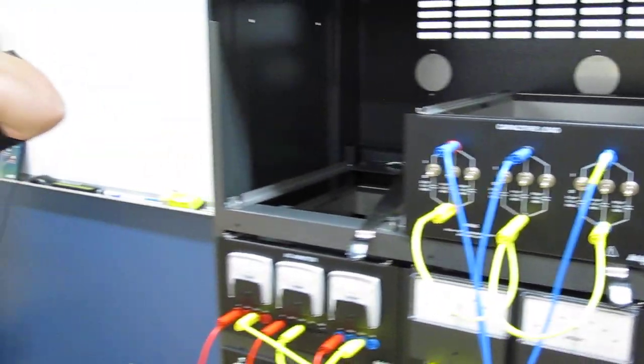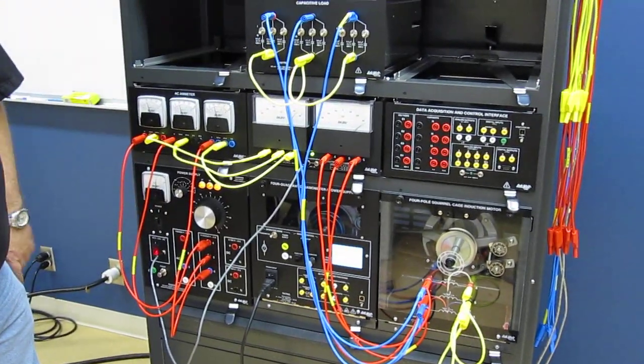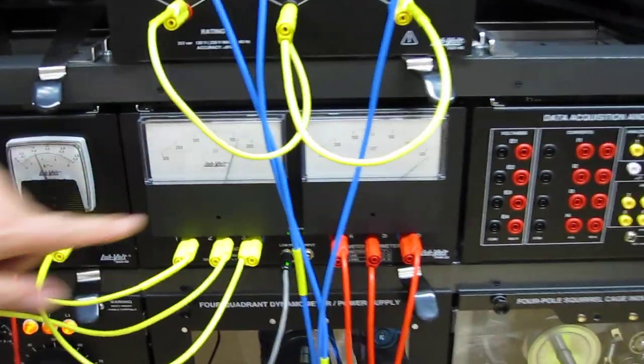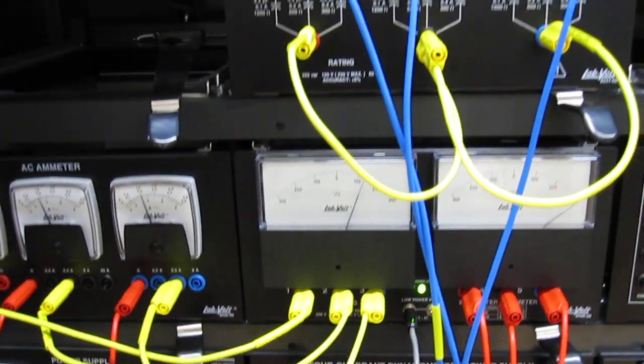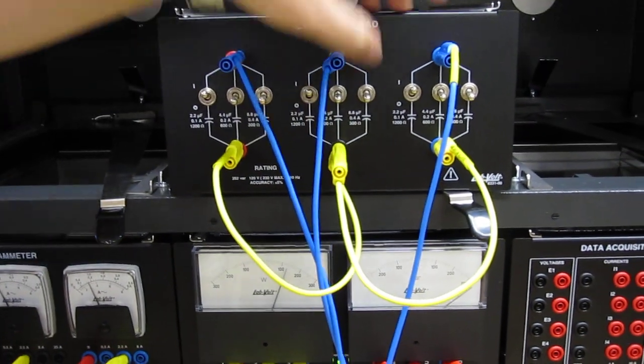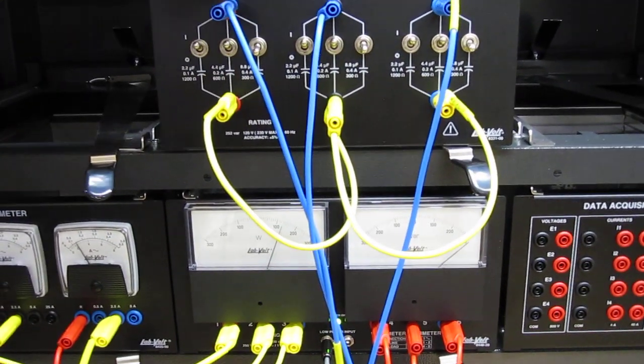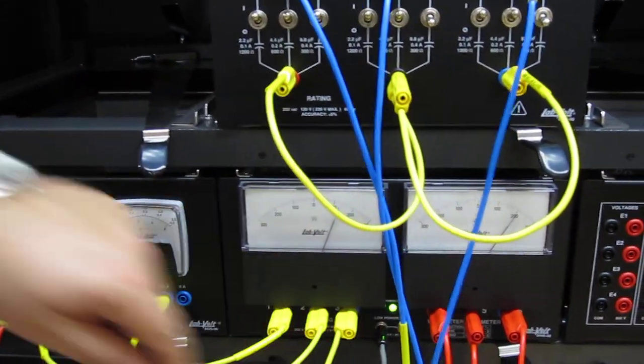Now all my switches are off. So when I start that again, I still have my bars that are really maxed out and my current is still around 1 amp. When I start adding capacitors on that, I see that the bars are going down.